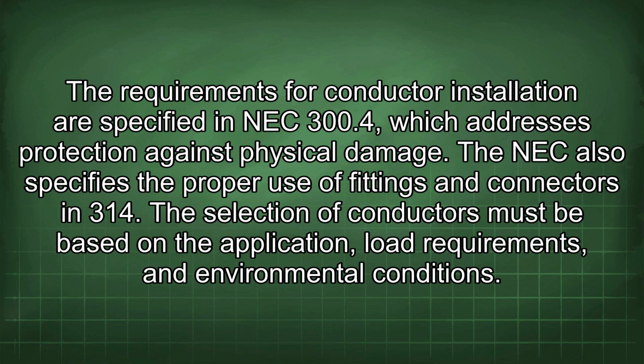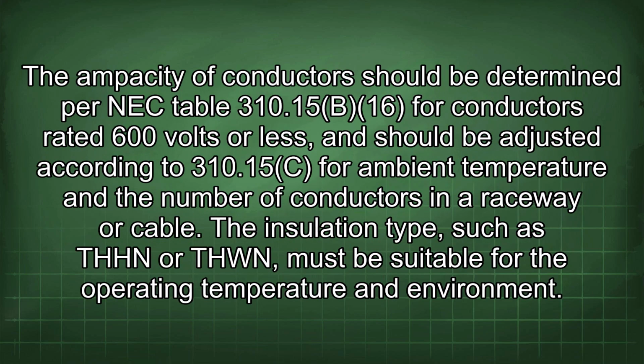The NEC also specifies the proper use of fittings and connectors in 314. The selection of conductors must be based on the application, load requirements, and environmental conditions. The ampacity of conductors should be determined per NEC Table 310.15(B)(16) for conductors rated 600 volts or less, and should be adjusted according to 310.15(C) for ambient temperature and the number of conductors in a raceway or cable.